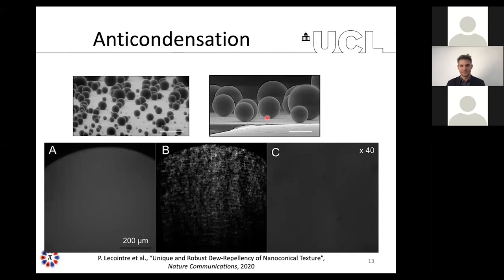Thank you for a great presentation. How much does this reduce overheating? It depends on the geographical location. I gave a number—you can prevent about 220 watts per square meter of glazing. You can go around your house, measure the surface of your windows, and start doing the calculations yourself. But we have been more rigorous than that. We have used building energy modeling software. We have compared our technology with normal windows. We have found that depending on the geographical location, in the warmer places like Italy, Greece, and so on, you can reduce the energy consumption for air conditioning by as much as even 40%. So it's not marginal, it's quite significant.